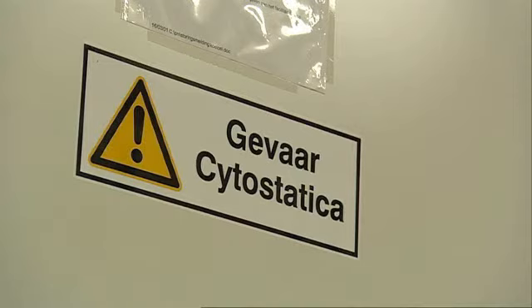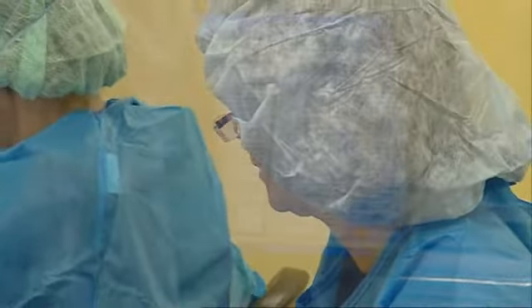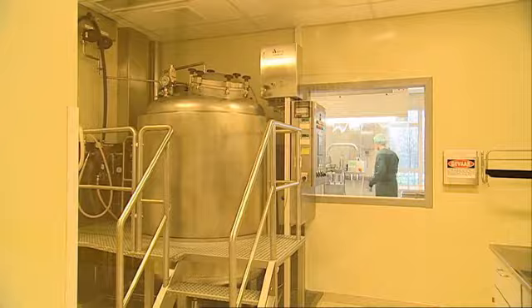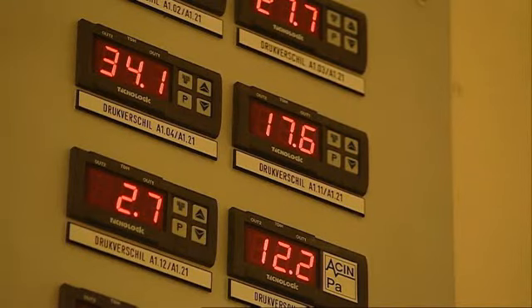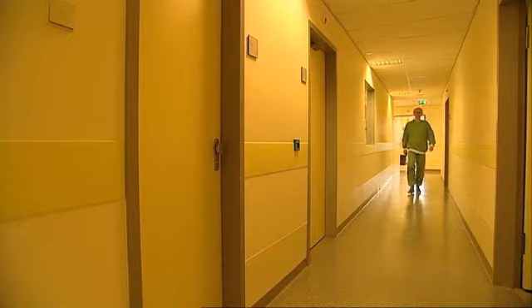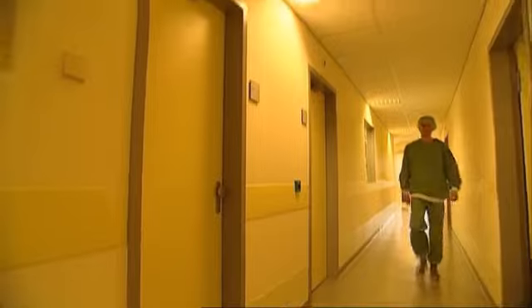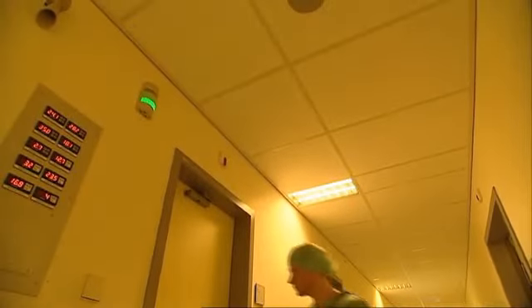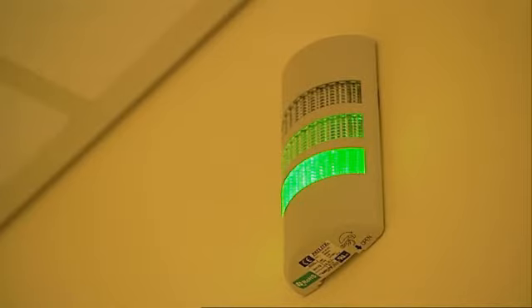The sterile production unit consists of several rooms where different operations take place. Each room has its own classification. Especially during production, pressure hierarchy has to be monitored. Visual monitoring includes alarm beacons. If they're green, you know the room is safe and in compliance. If they turn red, it means there's something wrong. This is accompanied by an acoustic signal.